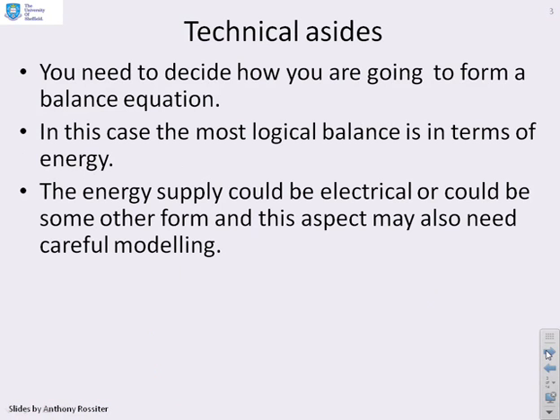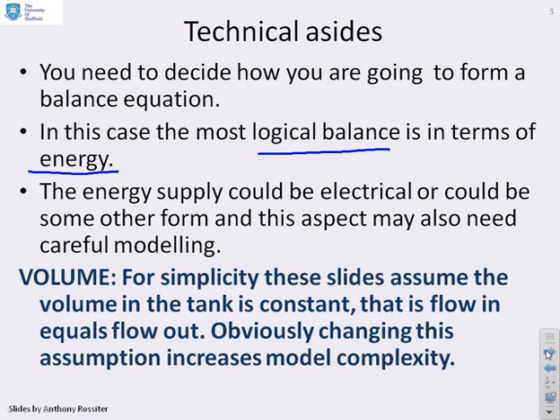Before we model this we need to think about how we're going to do it, and generally speaking with these process problems we've used balance equations. Because this is a heat exchanger the most logical balance to do is in terms of energy. The energy supply could be electrical, so that's the heater, or it could be in some other form. We are going to use steam as the main source of heat for the example shown here, but there are cases where it may be electrical and you'll need a slightly different model. For simplicity these slides assume that the volume in the tank is constant, so the flow in equals the flow out. If this assumption is not true you need to look at your modelling and be a little bit careful because the model will be slightly more complicated.